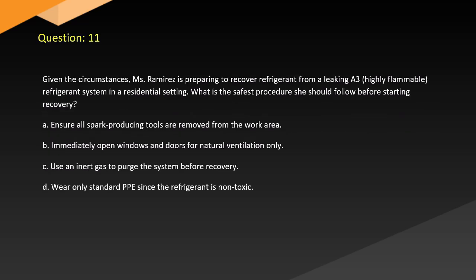Question 11. Given the circumstances, Ms. Ramirez is preparing to recover refrigerant from a leaking, highly flammable refrigerant system in a residential setting. What is the safest procedure she should follow before starting recovery? A. Ensure all spark-producing tools are removed from the work area. B. Immediately open windows and doors for natural ventilation only. C. Use an inert gas to purge the system before recovery. D. Wear only standard PPE since the refrigerant is non-toxic.